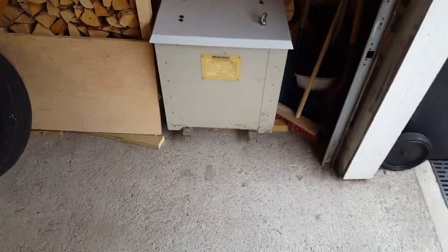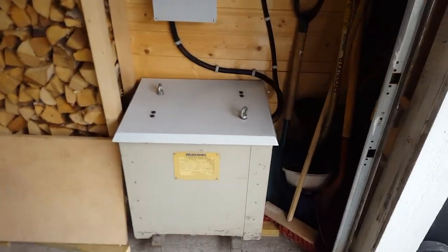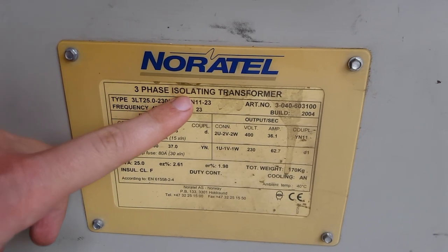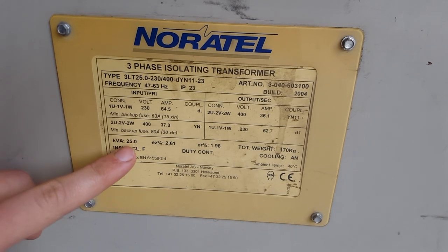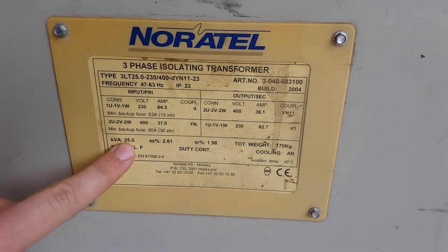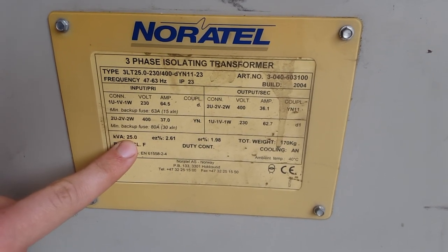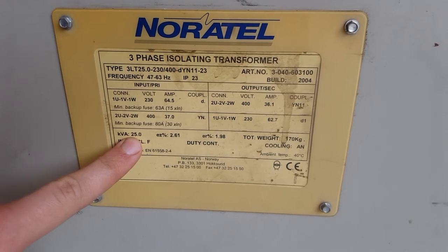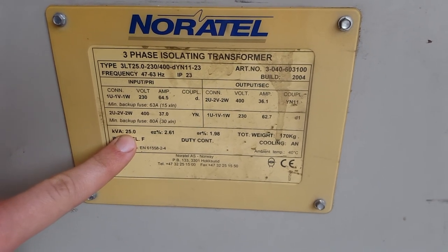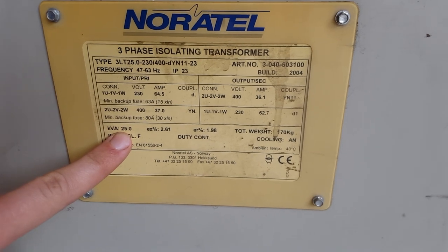So let's see, here is my charging station. Down there we have the transformer. This is a 3-phase isolating transformer, and since we are building a 22 kilowatt charging station we needed at least that amount of capacity. And this is a 25 kVA transformer.